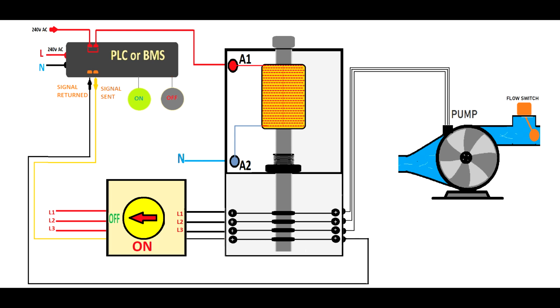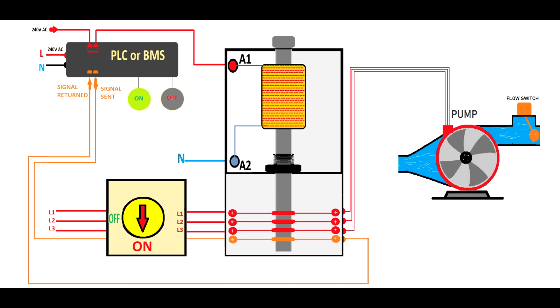One electrician goes there and says, well, someone by mistake turned off the isolating switch, or maybe a connection is broken somewhere. But that's not good enough, because you will turn on the isolating switch and now the pump is running, as you will see. The power circuit passes by and goes straight to the motor, the pump is running. At the same time, the signal wire is returning to the programmable logic control. And the guy will see that the pump is running. And this is good only in this situation.